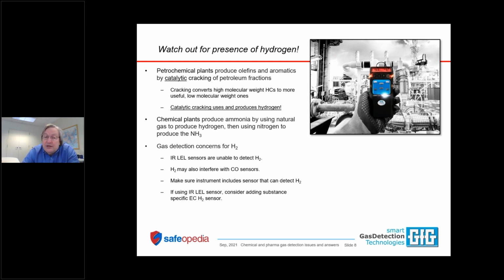So even though it is hydrogen nulled, it doesn't stop you from having alarms that might be due to the presence of hydrogen. If you need to measure the hydrogen, you can directly measure it by using an electrochemical sensor that's substance specific and designed to directly measure hydrogen. If you are using an infrared LEL sensor to measure combustible gas, I would strongly urge you to include a hydrogen sensor in the same multi-sensor instrument. If you don't do that, at least get familiar and comfortable with the effects of the hydrogen on your carbon monoxide sensor, the one that you're using in that instrument.